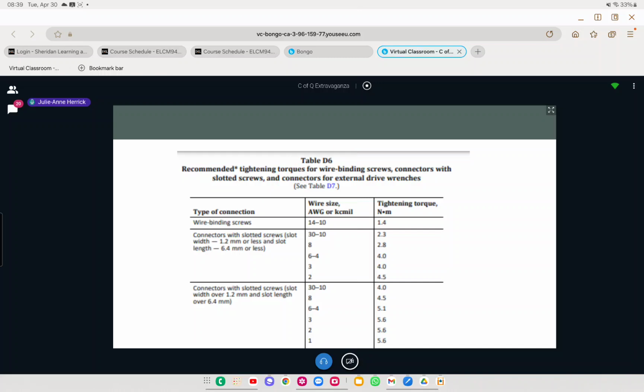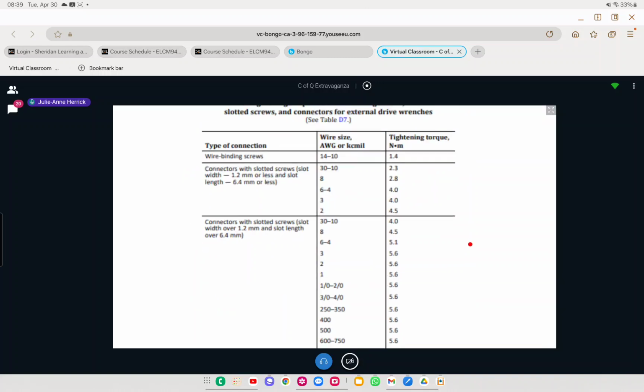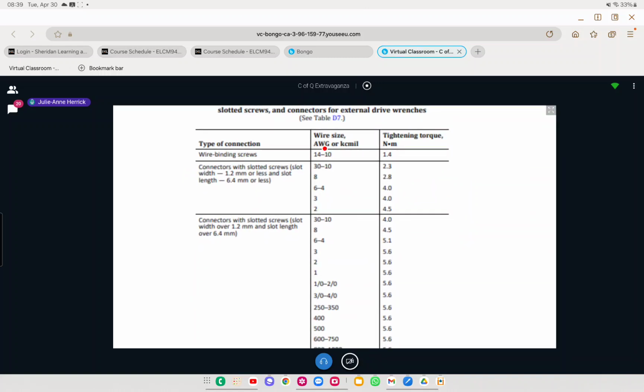Appendix D. What is the tightening torque in Newton per meters - because I think I gave you guys one of those questions yesterday, actually. So the wire size, it'll say number 14 for a wire binding screw. So there's between 10 gauge and 14 gauge wire binding screw, you have to do a tightening torque of 1.4 Newton meters.